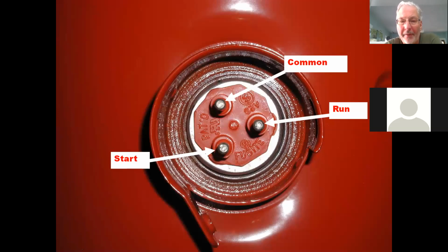Again, just a close up on there, common to run, common to start. And they're not always marked on the compressor. So you can write down on a piece of paper your three terminals and take some ohm readings. So if I go common to start and I see this value, say it is 2, common to run is 1, and then I go across these two and I get 3, that's the total. That tells me right there, that's my run and start.